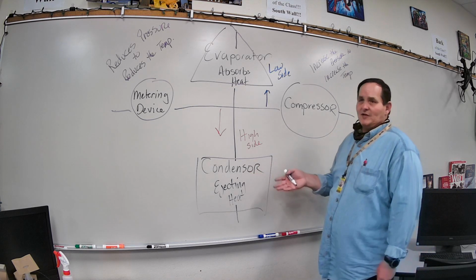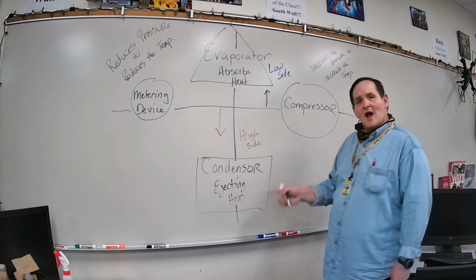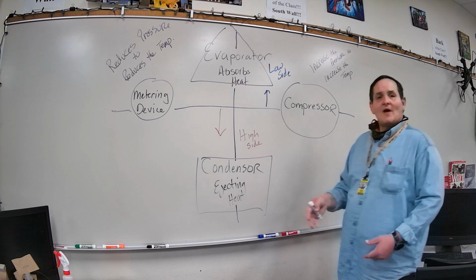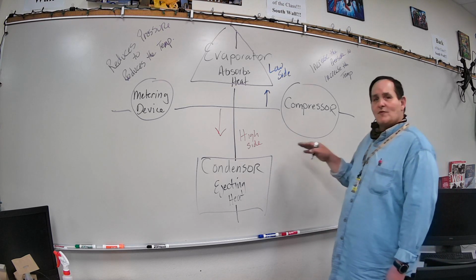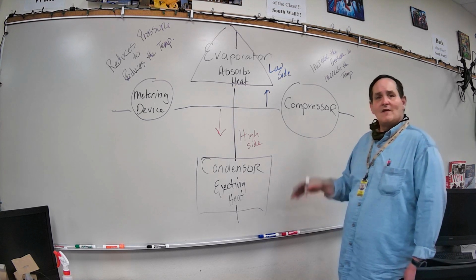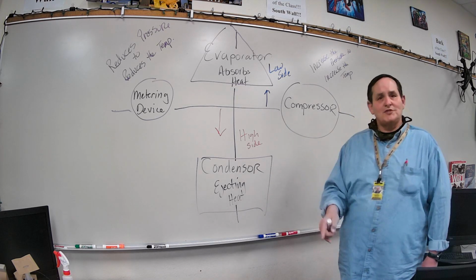Which in Abilene, the normal range is 95 degrees. So we have to have the refrigerant higher than the outdoor temperature, because how does heat move? It goes from a high to a low. So as long as the refrigerant is above 110 or 95 degrees, then the heat from the refrigerant will give itself up to the outdoor temperature.